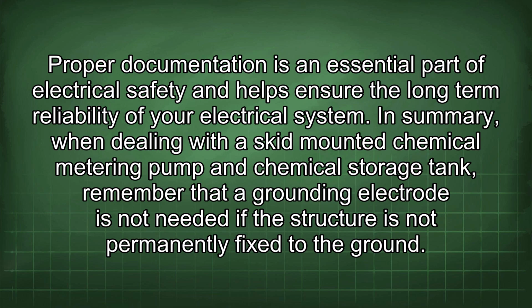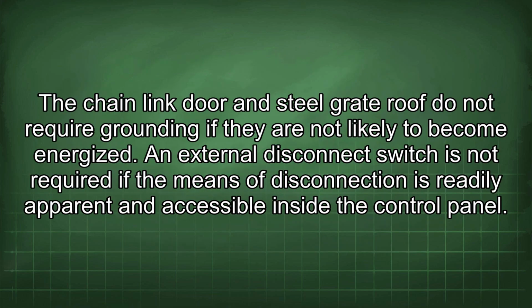In summary, when dealing with a skid-mounted chemical metering pump and chemical storage tank, remember that a grounding electrode is not needed if the structure is not permanently fixed to the ground. The chain-link door and steel grate roof do not require grounding if they are not likely to become energized.